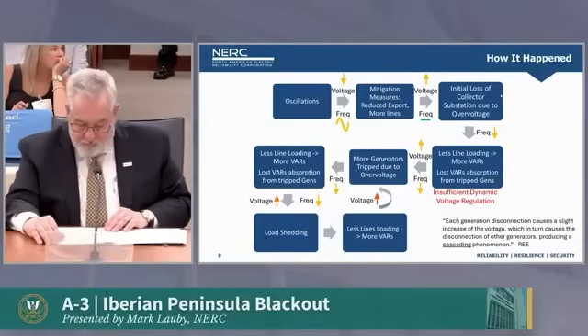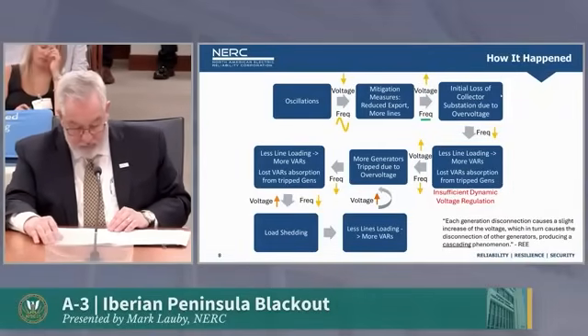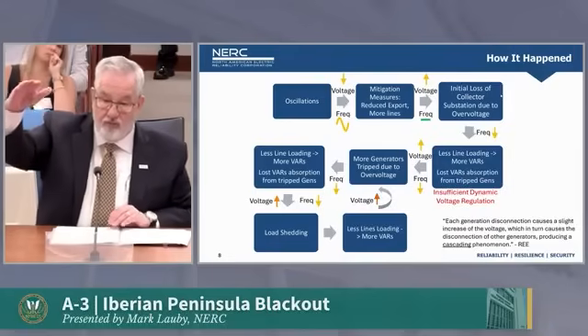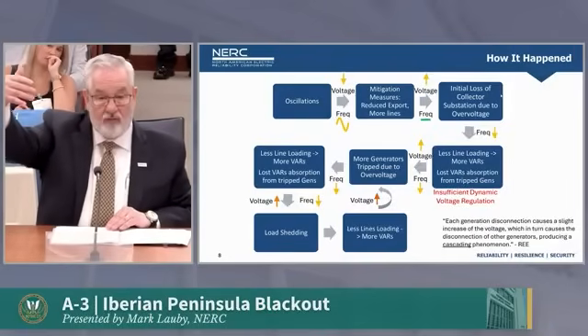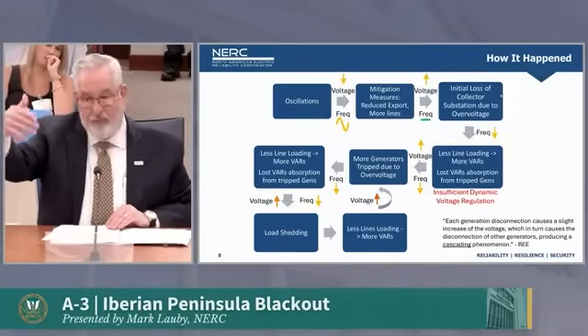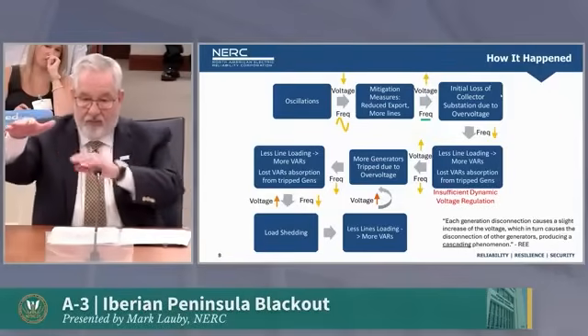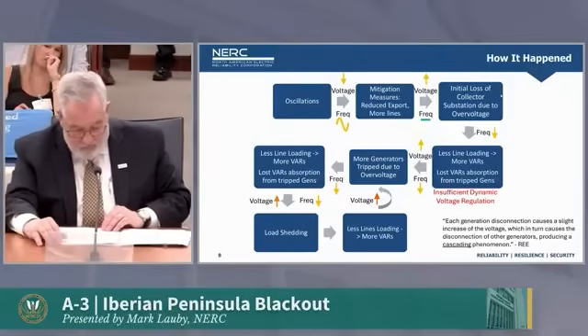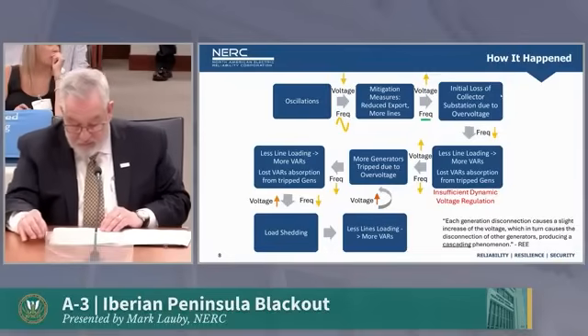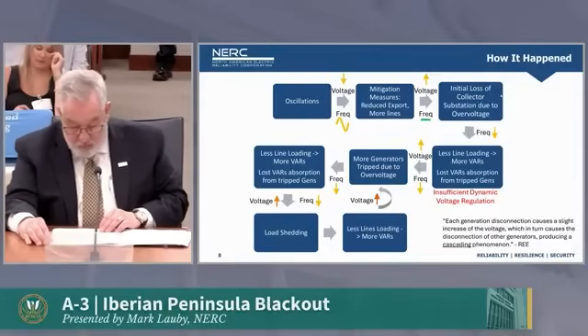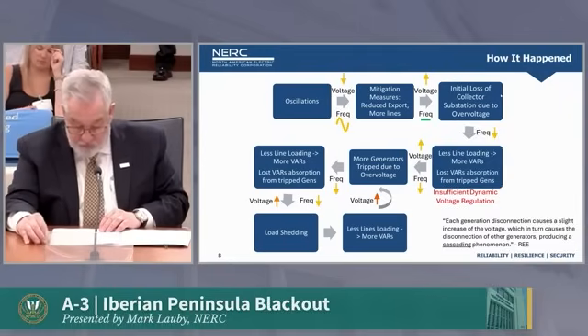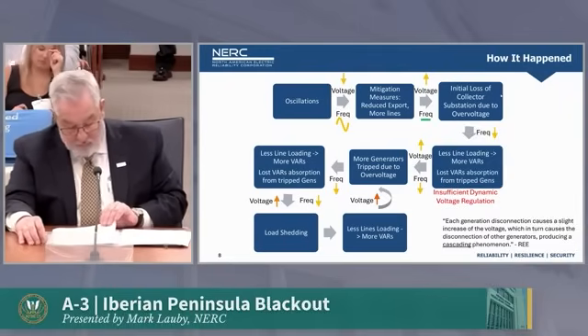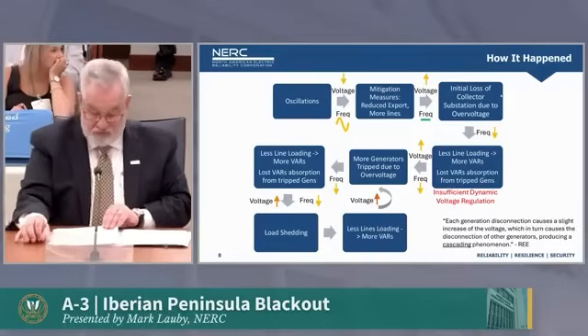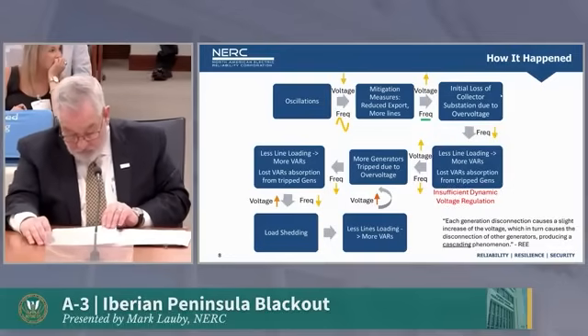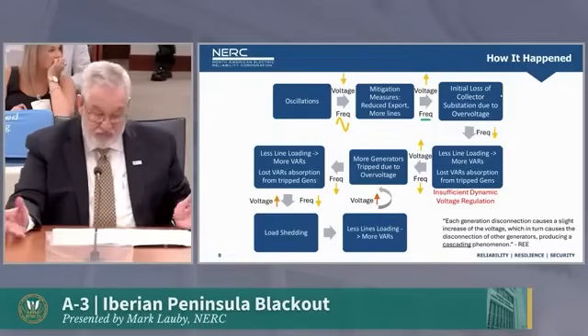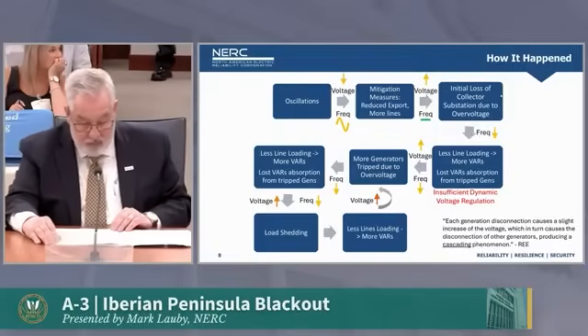Anyway, that all led to more overvoltages, causing more generators to trip, and this, of course, then drives voltage higher as the trip goes. The units trip, the lines are less loaded, voltage goes up, frequency comes down. It's kind of a death trap, right? You start doing that. Red Electrica puts it this way: each generator disconnection caused a slight increase in voltage, which in turn caused disconnection of other generators, producing a cascading phenomenon. When frequency got too low, under-frequency load shedding started. Shedding load further reduced loading on the transmission system, worsening the overvoltage conditions, and that extended the overvoltage problem.